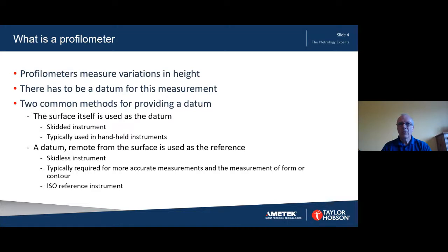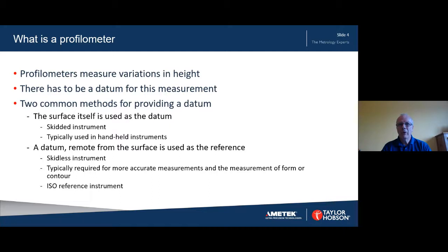With a skidded instrument the surface itself is used as the datum. A large radius skid rests on the surface and is used to follow the trend of the surface whilst the stylus measures variations between the surface itself and the skid's vertical position. This arrangement is highly practical and is often reserved for handheld instruments, which are easily adapted to measuring in different orientations on a component still mounted on a machining system. The second class of instrument relies on a remote datum usually embodied somewhere inside the instrument. Using a remote datum also enables measurement of form or contour, provided that there is a sufficiently accurate feedback of the gauging position in the traverse direction.